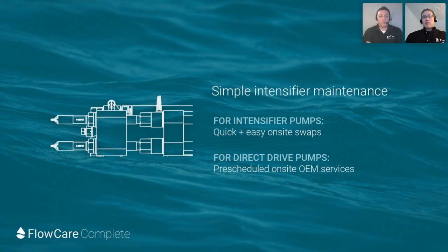We have an intensifier pump, also called a linear pump. For these pumps, Flowcare Complete actually swaps out the entire unit, similar to a full cartridge replacement. The tech comes on site, pulls the whole unit off, as shown in the diagram, and swaps it out for a brand new one.